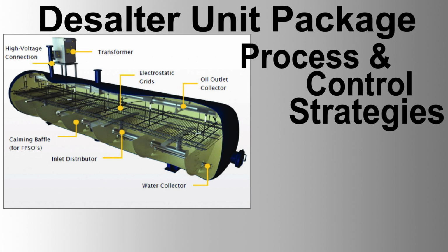2. Startup sequence. Start water injection and adjust the flow rate. Gradually open crude oil inlet valves for the slug catcher, separator, and desalter. Activate electrostatic fields and adjust voltage. Monitor levels, pressures, and flow rates, adjusting control loops as necessary. 3. Steady-state operation. Ensure all feed-forward, feedback, and cascade loops are functioning. Continuously monitor process variables and adjust as needed.